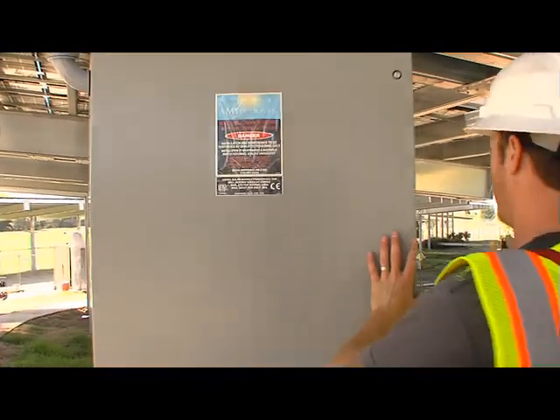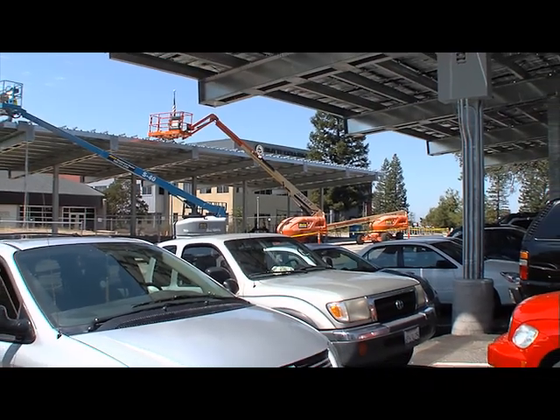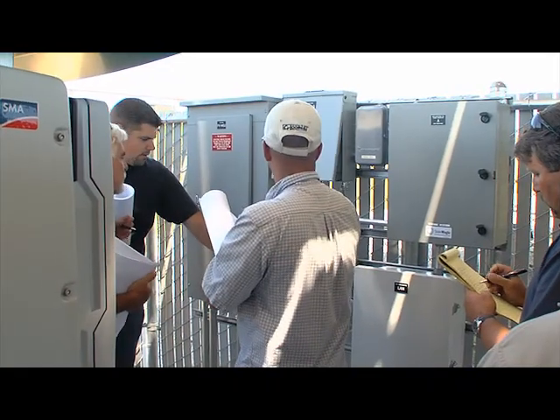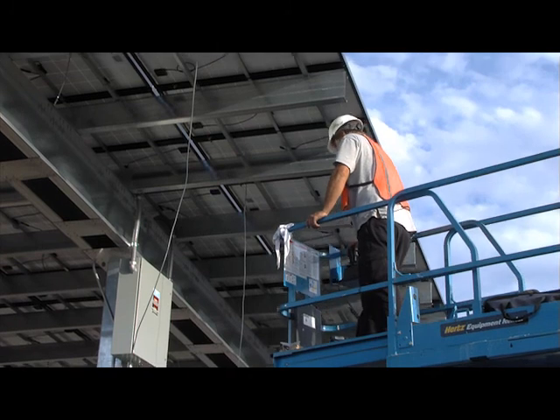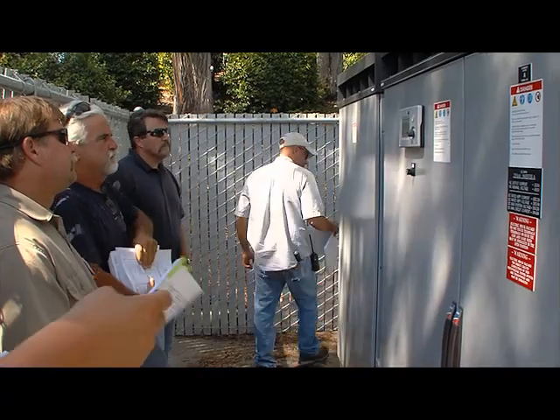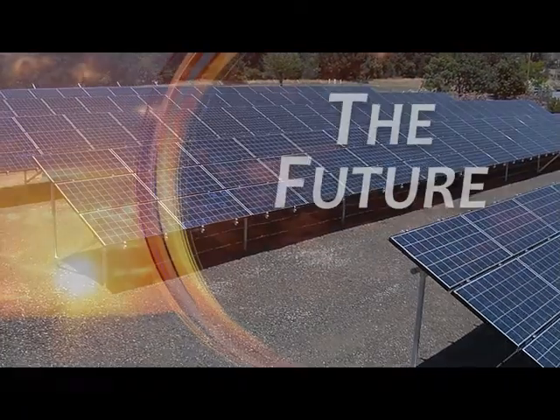Along with a 10-year performance warranty by the installer and a lifespan that may well go beyond 30 years, one of the best parts of solar generation is the relatively maintenance-free operation. Preventative maintenance will consist of yearly checks of the combiner boxes, electrical conductors, and solar inverters. To avoid power generation loss, the district is analyzing whether ongoing cleaning of panels that do not have their own watering system will be necessary.